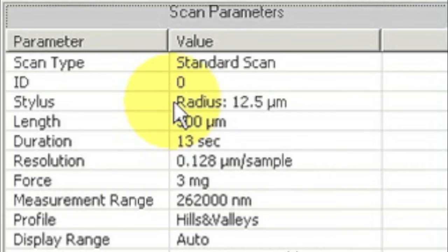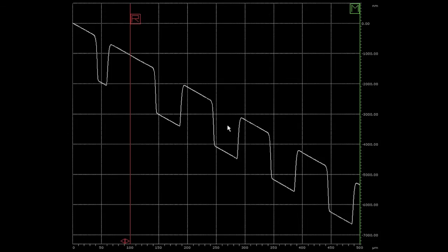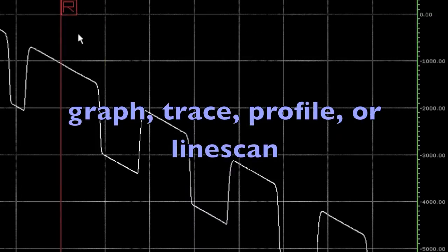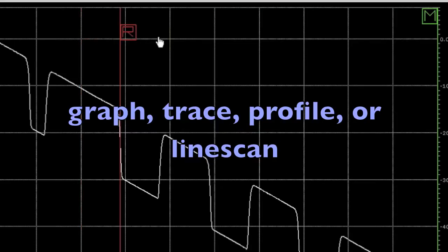Here we see a few of these parameters, including our stylus radius, the length of the scan, and the duration of the scan. Note that increasing the duration and decreasing the scan length both result in higher resolution scans. This is what we see in the sample positioning window when we're actually running our active scan routine. Immediately following the scan, a new image appears, which is a graph of the height versus distance data acquired.